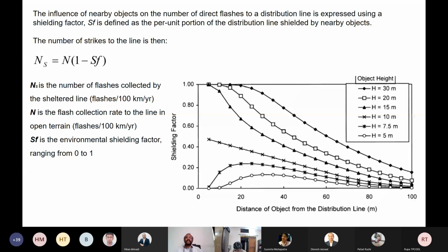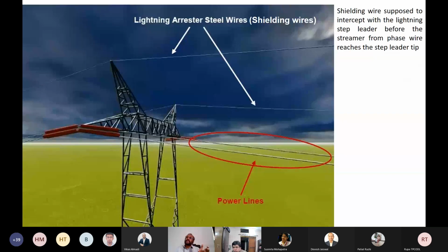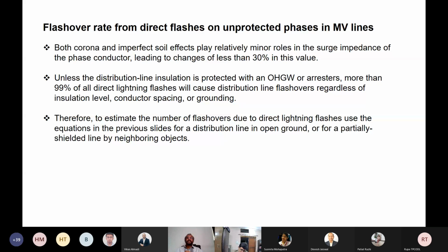And then lightning arresters, steel wires, shielding. Now we know that a shielding wire is supposed to intercept the lightning step leader before the streamer from the phase wire, so the shield wires play a big role in lightning protection. Now, flashover rate from direct flashes on an unprotected phase in MV lines: both corona and imperfect soil effects play relatively minor roles in the surge impedance of the phase conductor, leading to a change of about 30%, relatively small.